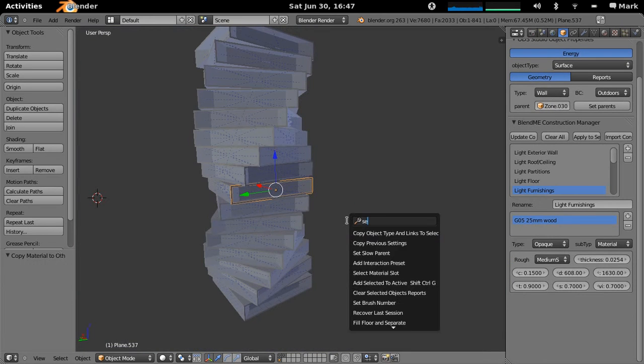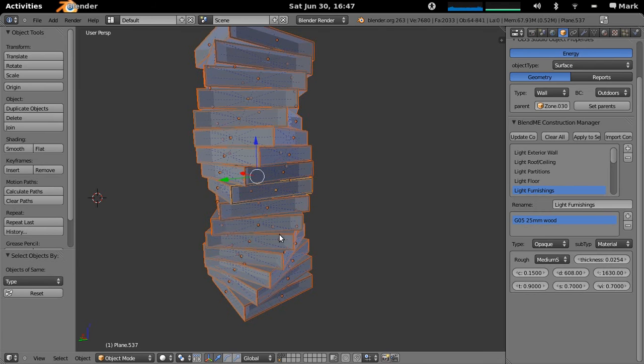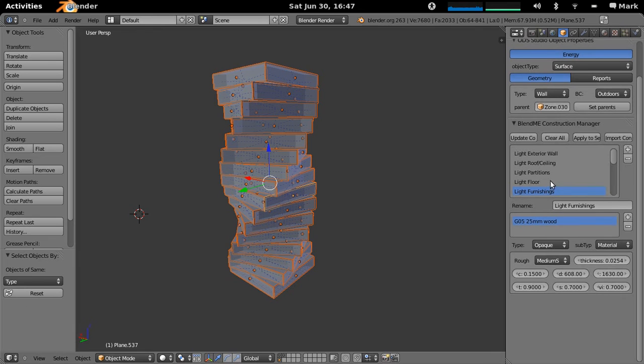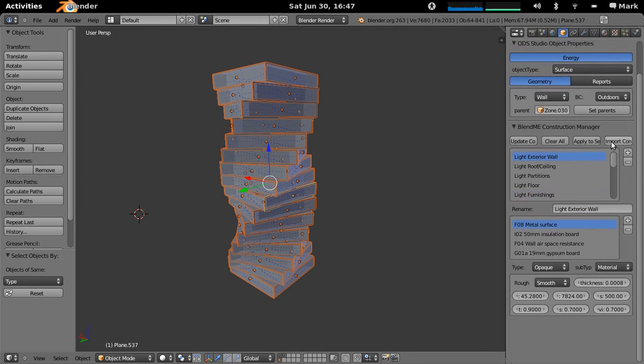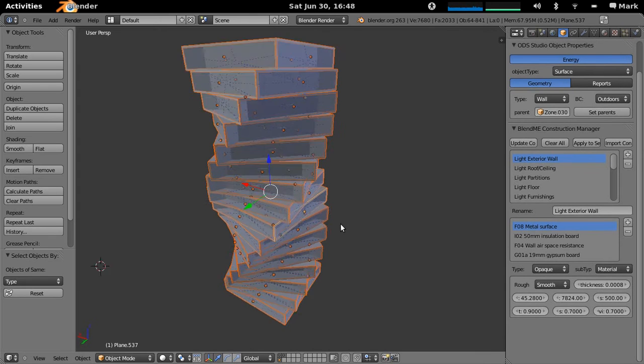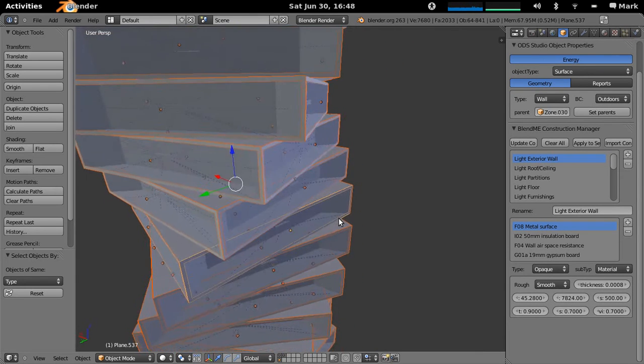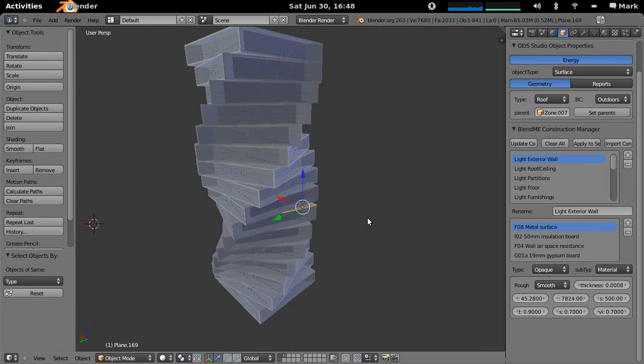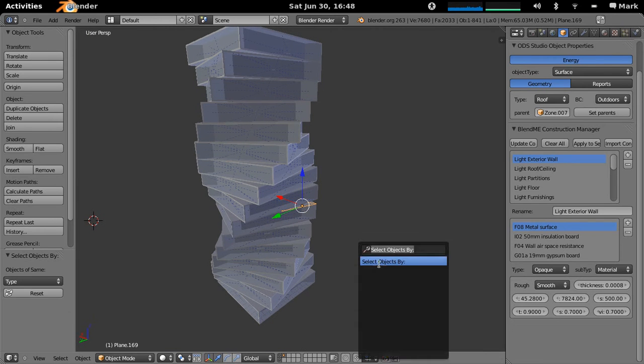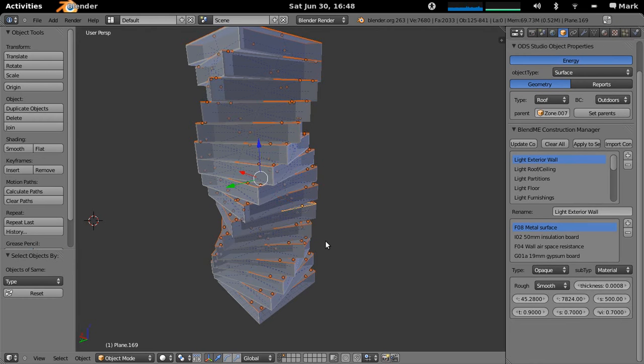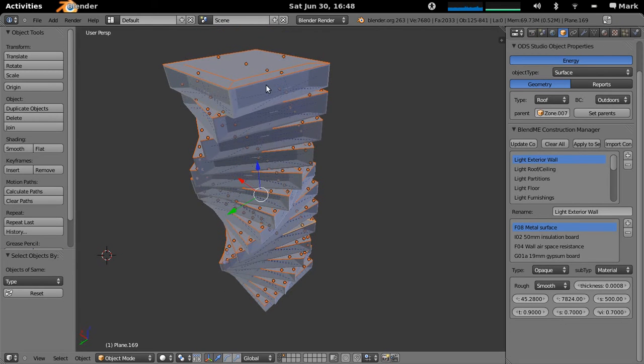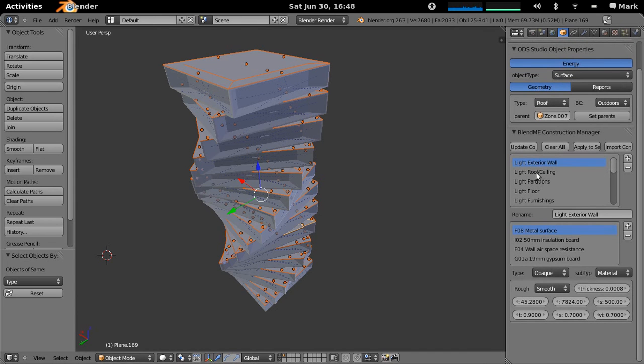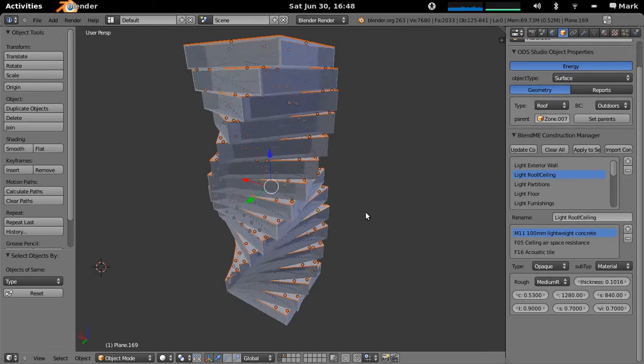What you just do is you will select all of your walls here. And select objects by type. So that's now selected all the external walls. And we'll select light exterior wall and we'll apply it to all selected. So now all these exterior wall objects have that type of construction applied to them. Similarly we can select all these objects here which are of type roof. So we can select objects of the same type. And these will all be roof type objects. So we can go light roof ceiling. And we can apply that to all selected.